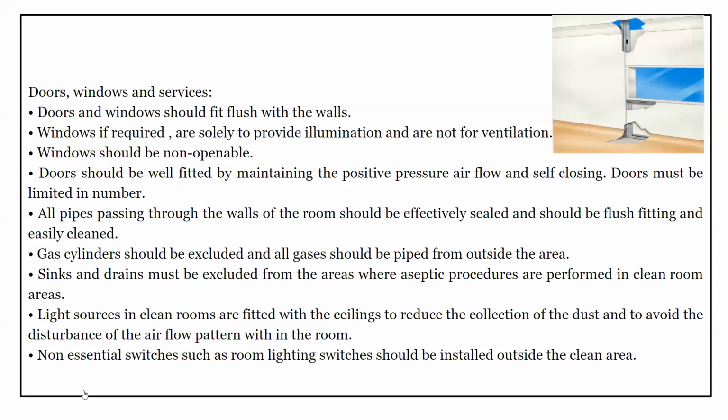It prevents ingress of exterior air into the aseptic area. Inside pressure is greater, so whenever you open the door for material flow or personnel flow, since the inside pressure is higher, the air will move from inside to outside, and thus it will prevent entry of exterior air into the aseptic area.